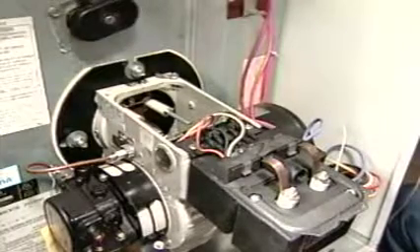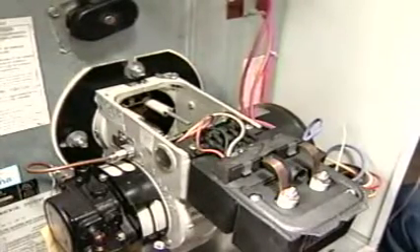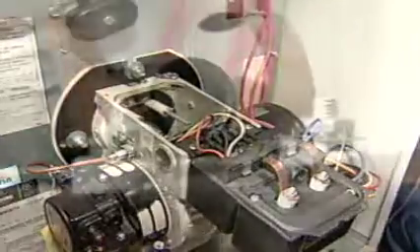The reset button is what's causing the furnace to shut down, but is it the root cause of the problem? Nope. To find out why it's tripping, you'll need your tools and your meter. The furnace is supplied with a primary control which provides interrupted ignition. This means that the ignition transformer is cut out of the circuit once flame is proven by the cad cell. The cad cell responds to light from the flame.